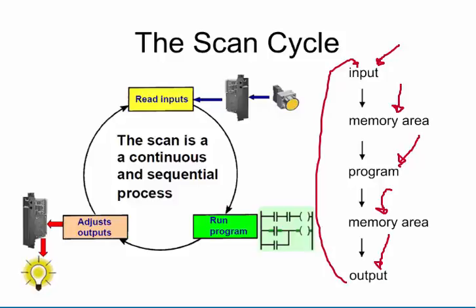The time by which the input is scanned, the output is set, and then the input is scanned again is referred to as the scan time. The scan time depends upon a couple of clear parameters: how many input and output units there are, the length of the program, and any other routine or function that is heavily influencing the mathematical or program capabilities of the CPU.